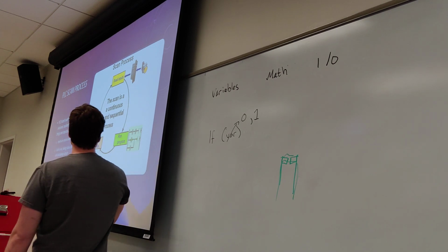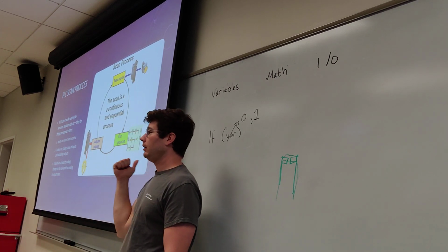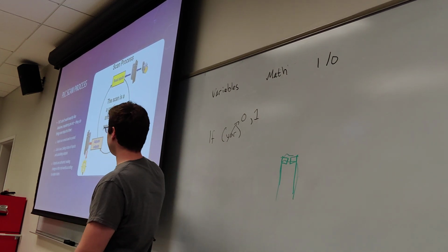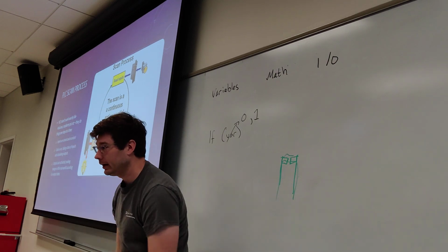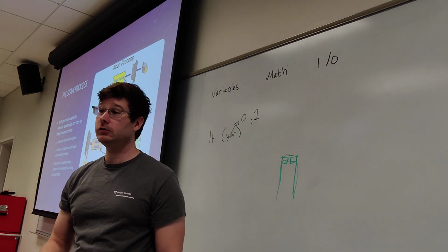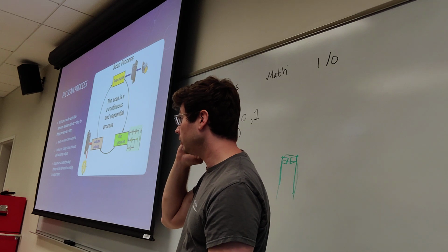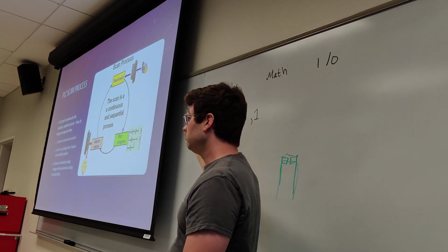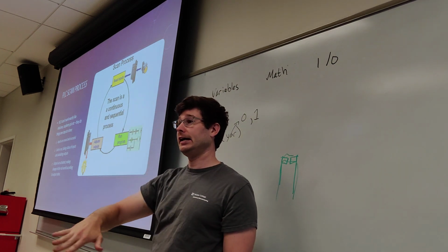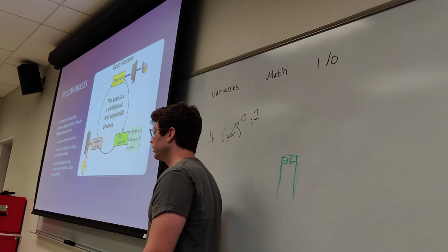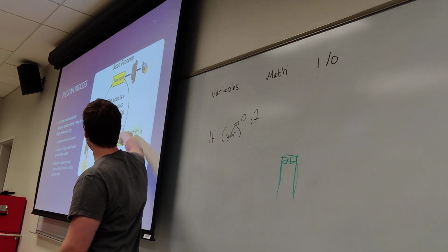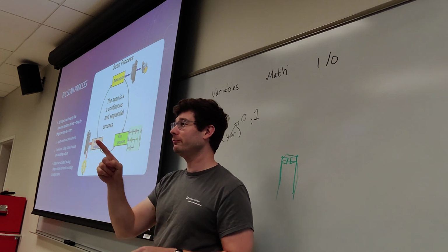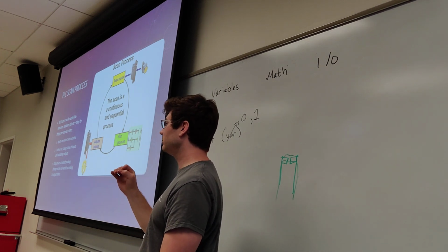Okay. Next, we run our program. So if we're doing things like saying variable 1 plus variable 2 equals variable 3, that's where this step will happen. All of that stuff gets evaluated in one go. Things to note: if you set something higher in the program, for example, x equals 1 on line 1, and then later on line 50, you have x equals 0, the outcome of running that whole program will be the end result. You know what I mean? So if you set it to 1 first and then later set it to 0, it will still be 0 at the end of all that.